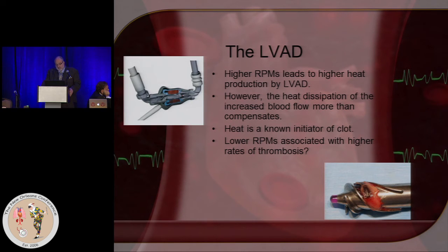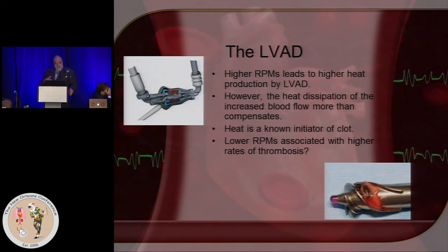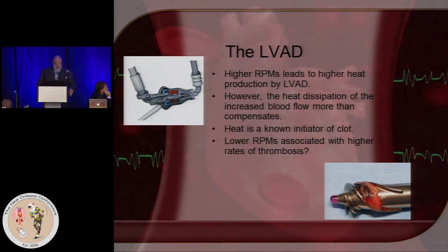Now to the VAD itself. Higher RPMs lead to higher heat production — true for any technology. However, even more important is that heat dissipation from the pump itself increases as blood flow passes by. So although you're producing more heat, the net effect because of increased blood flow is actually greater washout of heat. Heat is a big culprit in the formation of thrombus. So there is reason to think higher RPMs produce greater washout and therefore lower thrombus rates, but we don't know that for sure — not enough data yet.